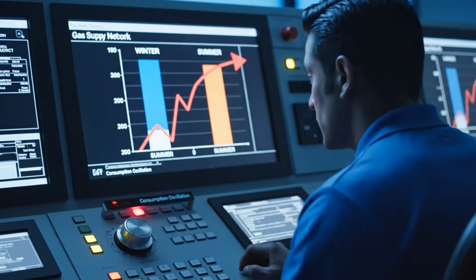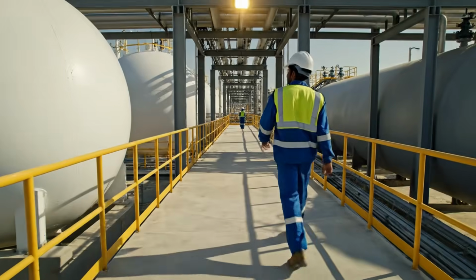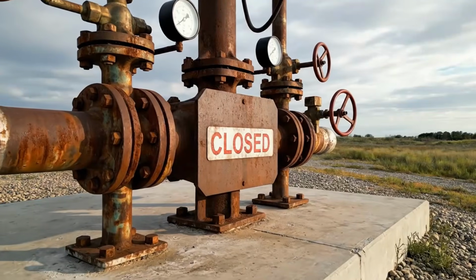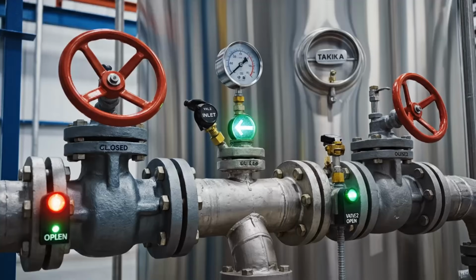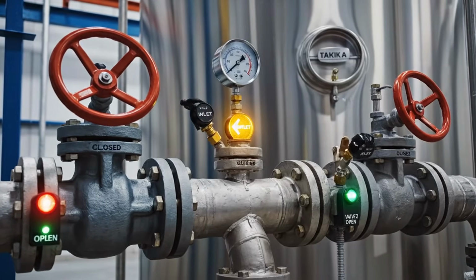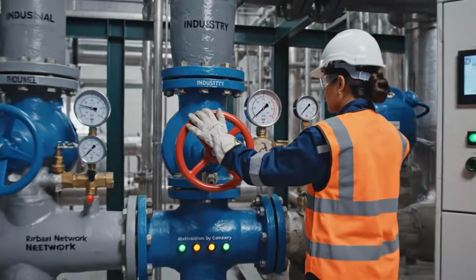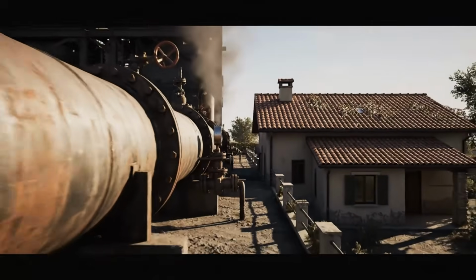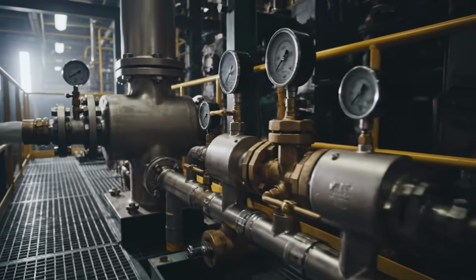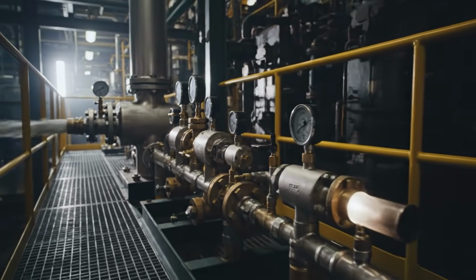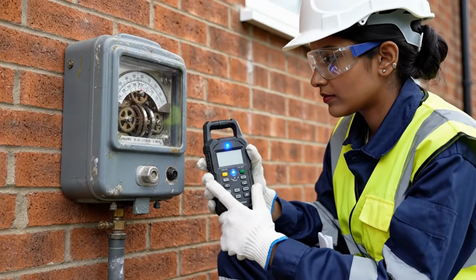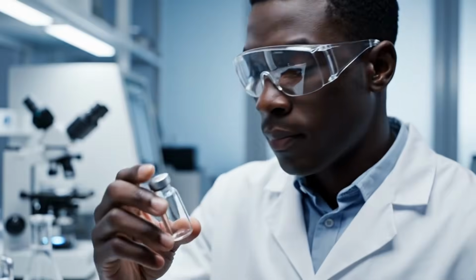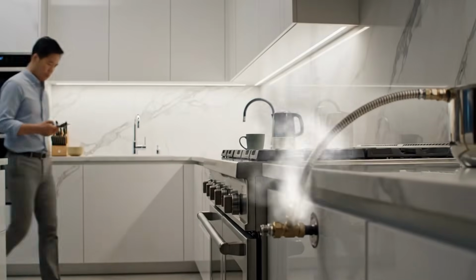In this final stretch, an essential operation for public safety also occurs: odorization. Pure natural gas is colorless and almost odorless. A leak under those conditions would be much harder to detect. Therefore, odorant compounds are added in minimal but easily perceptible concentrations. That intense and characteristic smell is not naturally present. It is incorporated deliberately so that any leak is immediately noticed in homes, businesses, or industrial facilities.